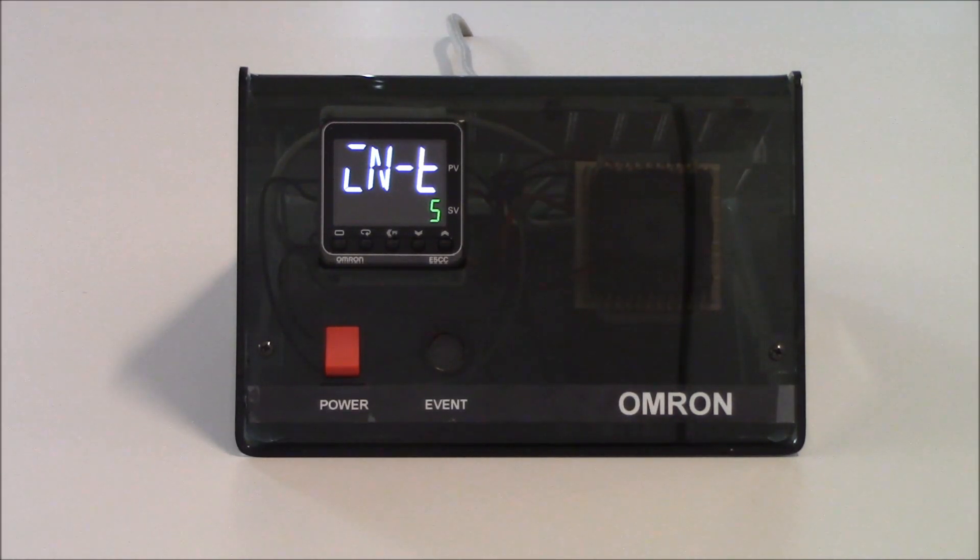Our very first parameter in the initial setting level is our IN-T parameter, which is our input type. For all the various different inputs that we can use for this unit, there's a number assigned to each one. In the instruction sheet provided with the unit, or the data sheet and user manual on our website, there is a chart showing the various different numbers you can assign to different inputs. With thermocouples and RTD style sensors, you'll have several different numbers for each type.